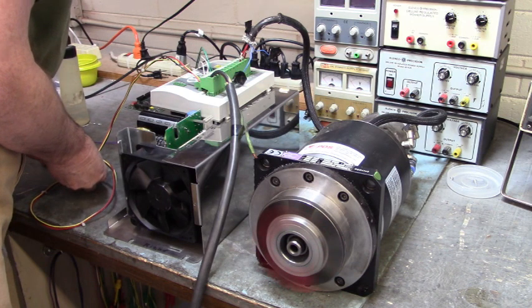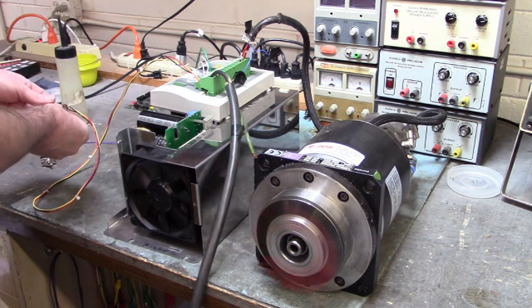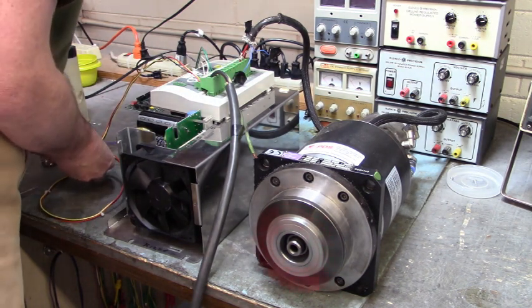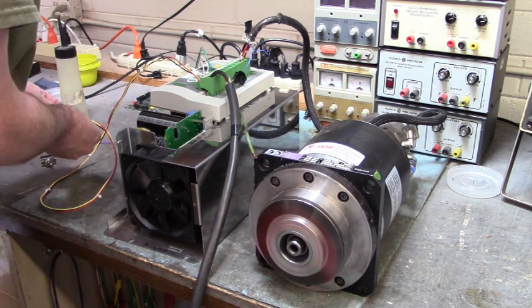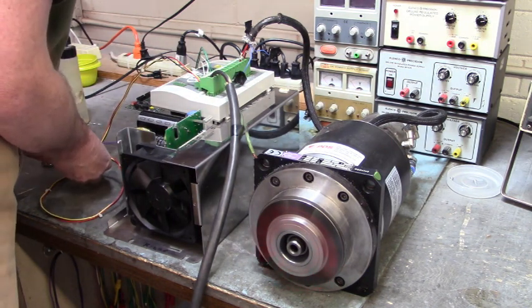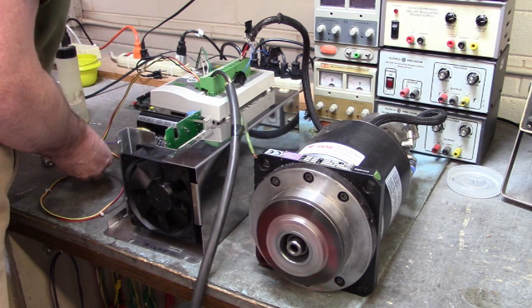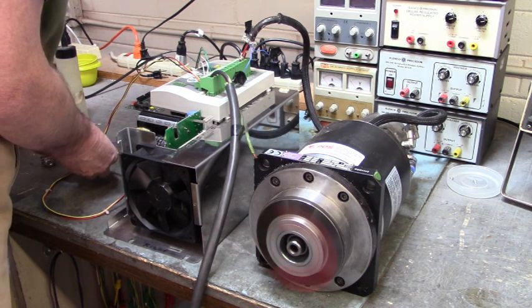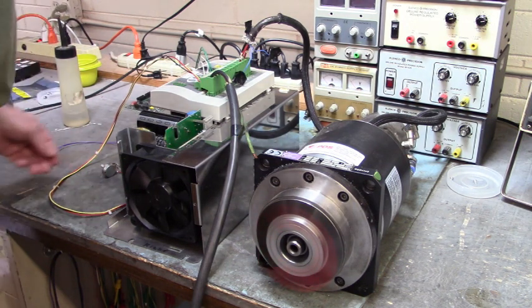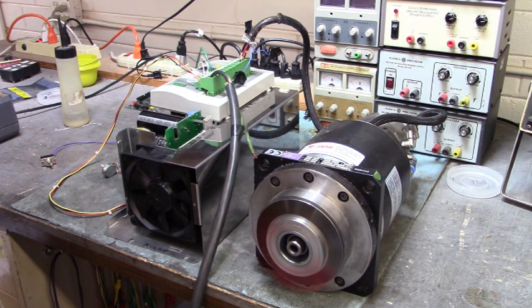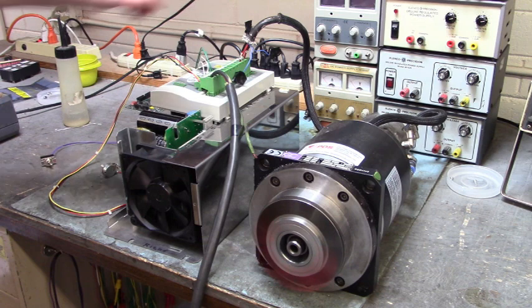That's 38.7 hertz right there. This drive is set to run up to 300 hertz. I'm not going to take it up that high. No need. I'm going to go get the Fluke oscilloscope and we'll take a look at the UVW waveforms.